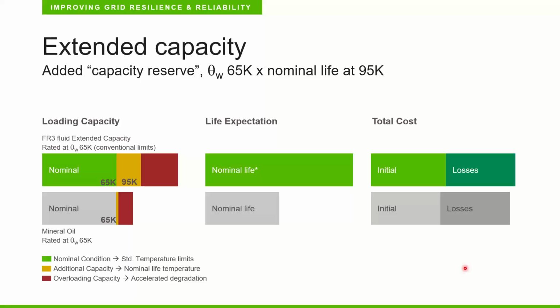If we think about the loading capacity, if we have a 65 K traditional transformer design, we have that orange part, which reflects this 30 degrees increase that's allowed by the standard in the capacity of the transformer without jeopardizing the nominal life of the transformer. It means we have an added capacity of the transformer. A second part is the red one, that is the overloading capacity of the transformer. The standard allows exceeding the limits of the temperature for a certain time with an accelerated degradation of the paper of the insulation system. And we can see how this is much bigger with FR3 fluid than with mineral oil.